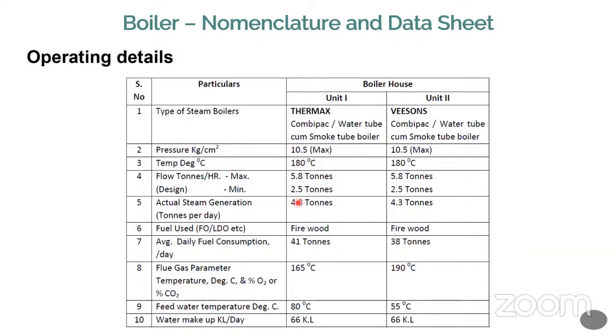Okay. So if your requirement is below that and you are operating there, then the boiler efficiency will come down. And similarly, you should not go above that one. That means the boiler will be overrated. It is similar to operating a motor at a very high load condition, more than 100%. Normally, it is not advisable for a longer time, but for a shorter time it is acceptable. And similarly, the actual steam generation, this is an average value, is going to be 4.8.